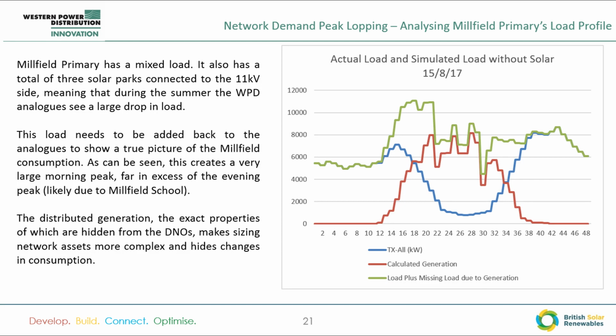We're trying to analyse the primary's load profile, and there's a slight issue. This is taken from WPD's analog, so their internal data monitoring system. You can see that we've got generation data from only one of 3 solar parks that are connected. There are 2 5-megawatt parks, which are the same design as each other, Higher Hill Farm and Butley. And then there's the little Copleywood Park that we have the detailed generation data for.